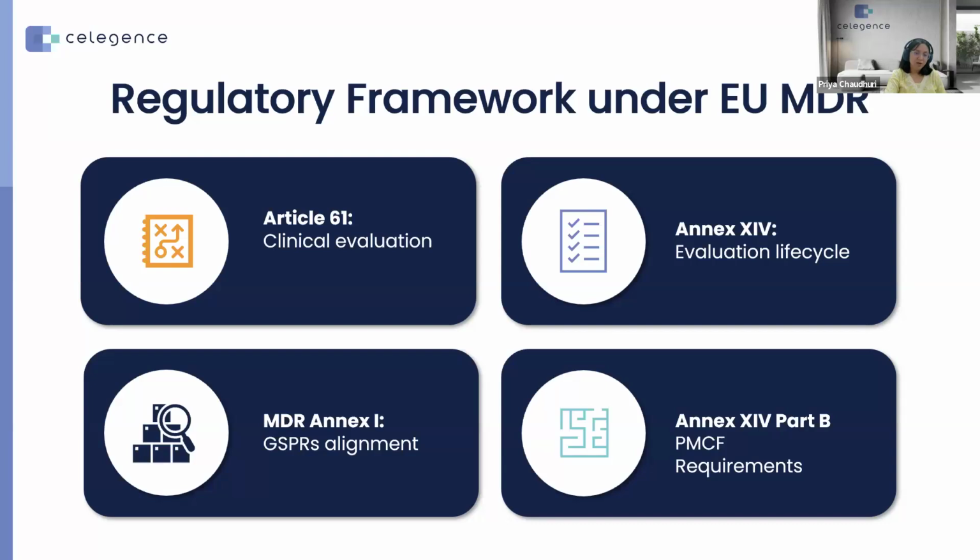And finally, Part B of Annex 14 outlines the requirements of the post-market clinical follow-up, the PMCF. It's a key requirement of collecting real-world performance and safety data, which is essential and required nowadays by almost all the notified bodies, irrespective of the class of the device, through various sources like surveys, case series, case studies, registry tracking, literature, as well as a PMCF study if there is one.